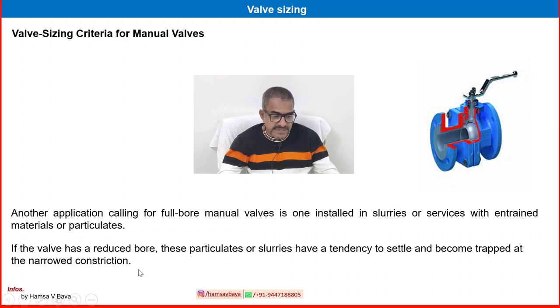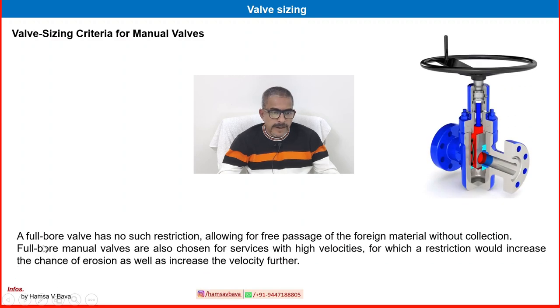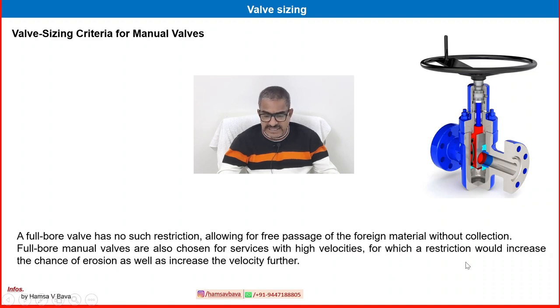Another application calling for a full bore manual valve is one installed in slurries and services with entrained material and particulates. If the valve has a reduced bore, these particulates and slurries have a tendency to settle and become trapped at the narrowed constriction. A full bore valve has no such restriction, allowing for free passage of foreign material. Full bore manual valves are also chosen for high-velocity services, where a restriction would increase the chance of erosion.